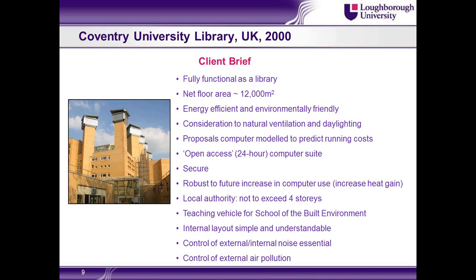We couldn't exceed 4 stories because of the local authority planning restrictions. They wanted the internal layout to be simple and understandable. Control of external and internal noise was essential. There's a raised ring road just outside, so it became important to provide some control for that. So opening windows on the perimeter was a no-no, really. We had to think of an alternative way of designing the natural ventilation strategy.